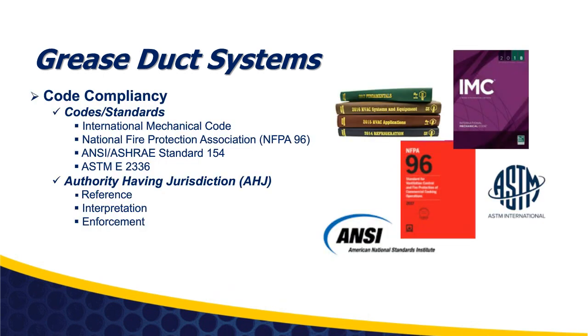So let's look at what the requirements would be to design and construct a grease duct system. So we're going to really look at codes and standards that are out there for reference for proper system design and construction. And we're really going to look at International Mechanical Code. I kind of put the International Mechanical Code all the time in this presentation. Uniform Mechanical Code also addresses grease duct systems, but if you look at them side by side, they're almost comparable, so I didn't feel it was pertinent to have both in here. National Fire Protection, NFPA 96, talks extensively about grease duct systems. There is reference in both of these to ASHRAE ANSI Standard 154. And then there's an engineering standard 2336, which also addresses fire resistance ducts for grease ducts.